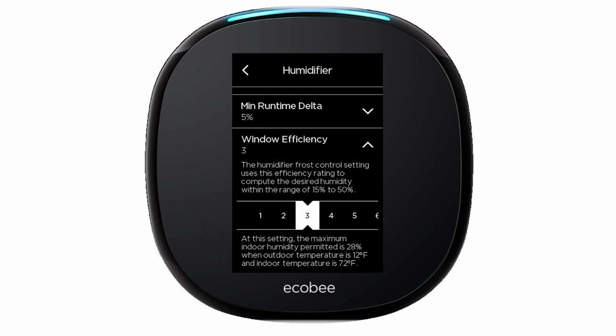So it's pretty cold outside. It's not going to let that humidity get real high in the house because you're going to start getting condensation building up. You can kind of adjust this as high up to when it's 12 degrees out. Indoor 72 is going to be 50% humidity in the house. So it's going to be pretty high during the winter time at a 7. Probably recommend you keep it at like a 3 or 4.